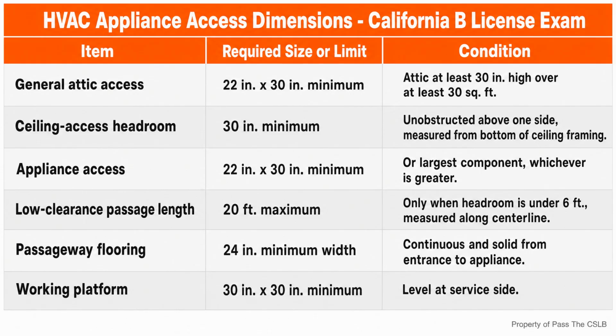Once an appliance is located in the attic or underfloor space, the California Mechanical Code adds a more practical test. The opening and passageway must be at least 22 inches by 30 inches or large enough for the largest component of the appliance, whichever is greater. The phrase, whichever is greater, matters more than the memorized minimum. 22 by 30 is not a universal answer that excuses the contractor from checking the actual equipment. If the largest component needs a larger, clear opening for removal or replacement, the opening has to be larger. I would verify that before the framer closes the access, before the mechanical installer blocks the route, and before drywall turns a simple correction into demolition.